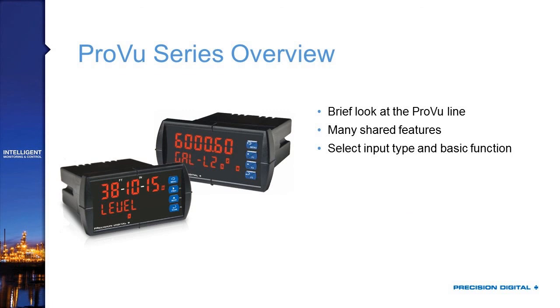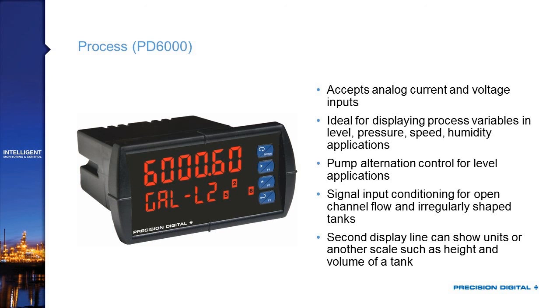Now let's take a brief overview of the ProVu series to understand the meters these new features go with. The PD-6000 is your standard ProVu — a basic process meter that accepts analog current and voltage inputs. It's ideal for displaying essentially any process variable coming in as a voltage signal or 4-20mA. You can scale it to display whatever you want, and then configure outputs based on that.